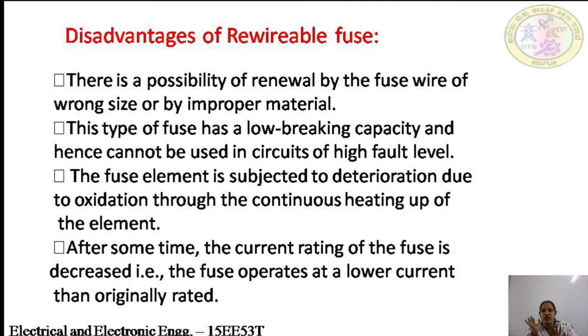So when there is a continuous flow of current, or continuous load, oxidation automatically takes place, and the current value changes. Whatever rated current we have, say it is designed for 10 amps, instead of the rated 10 amps the fuse wire will operate at only 8 amps. If the current increases to 8 amps, then the fuse will blow out. So that is one drawback or disadvantage of the rewirable fuse.